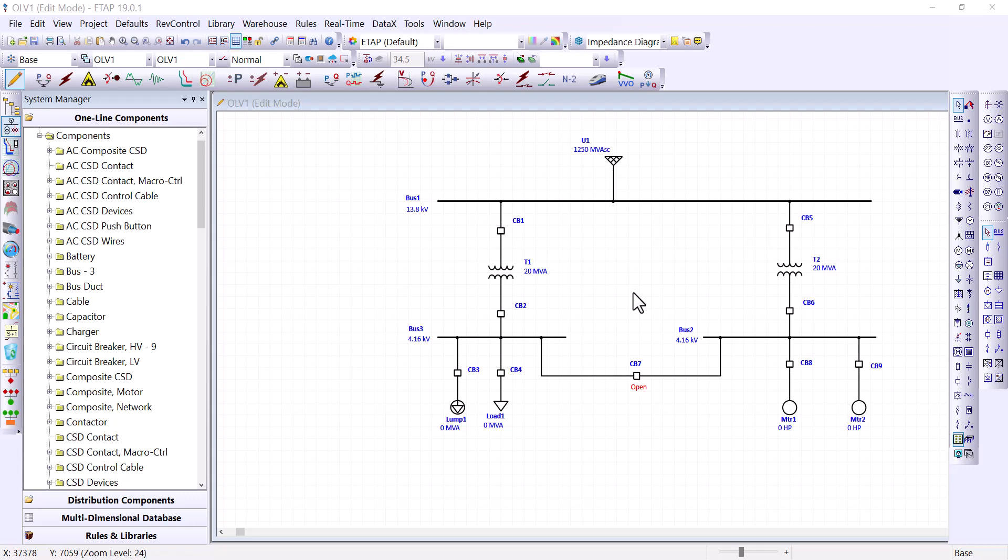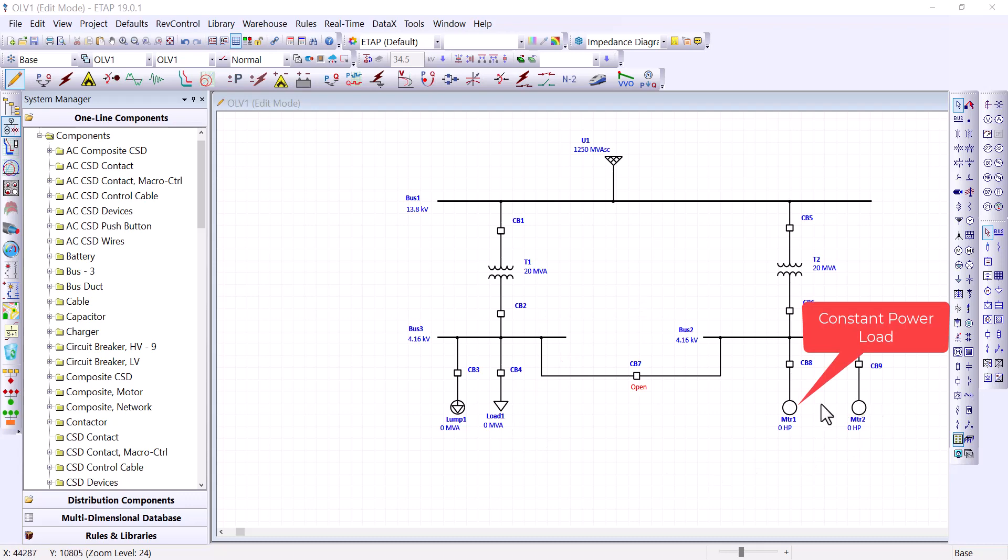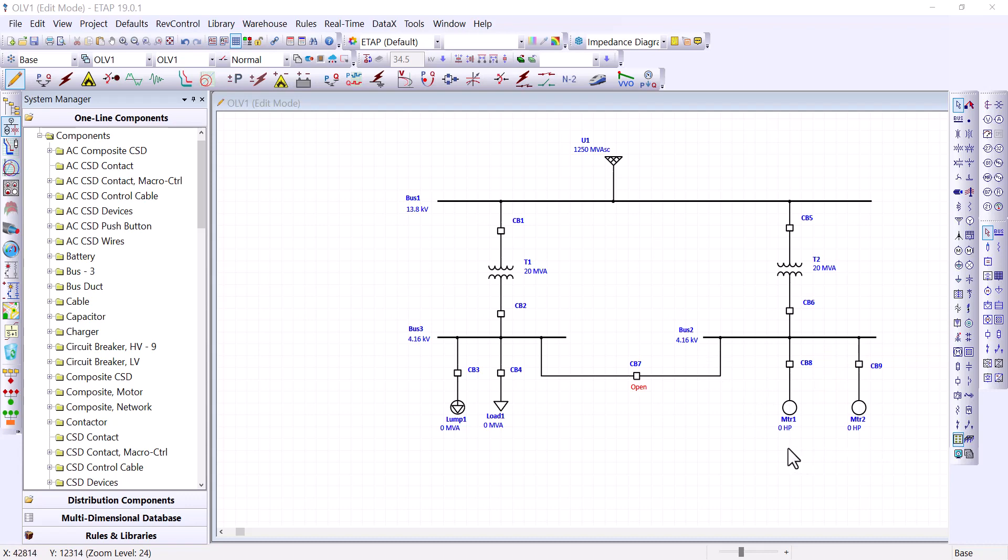Now let's move down to discuss some loads and discuss different types of loads. As you probably know, not all electrical loads behave the same. Therefore, loads can be classified as constant current loads, constant impedance loads, or constant power loads. And we will start with bus two, which contains AC induction motors. And motors are considered constant power loads because the output power remains constant despite the change in voltage. For example, if the motor terminal voltage sags to some limits, the current must compensate and increases proportionally to maintain that power constant.